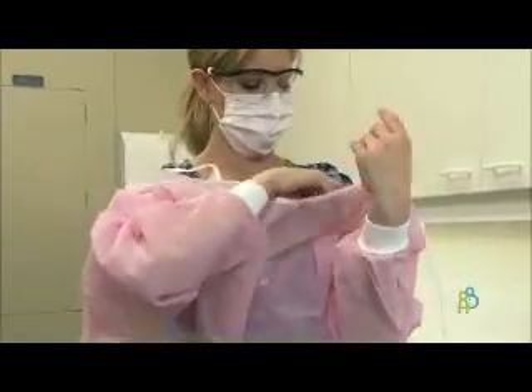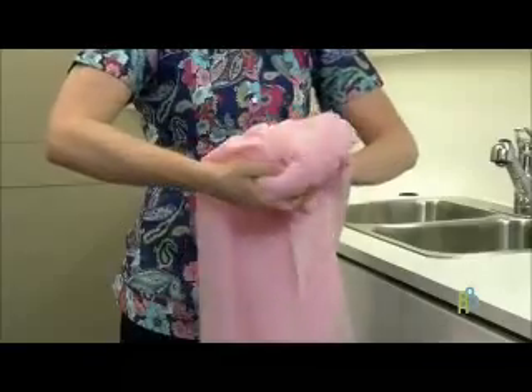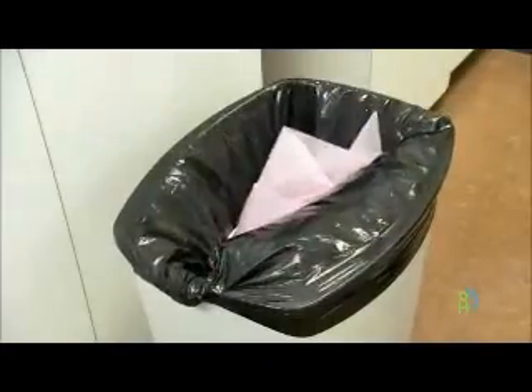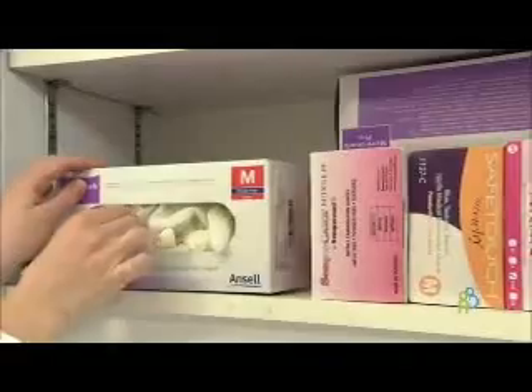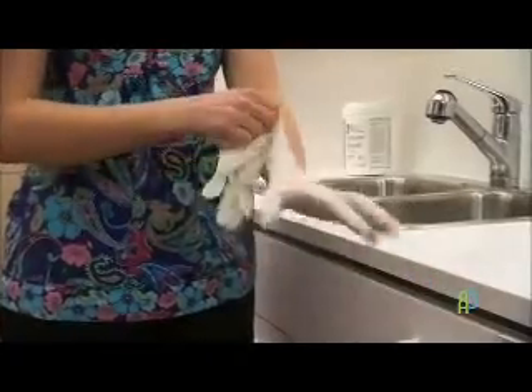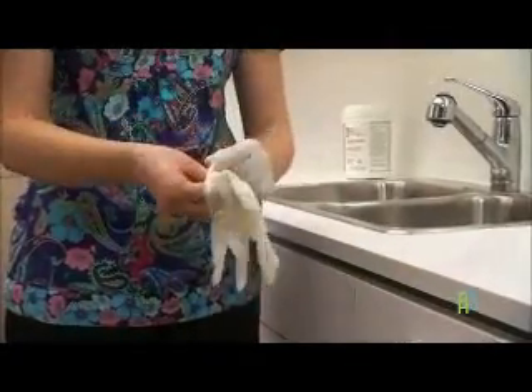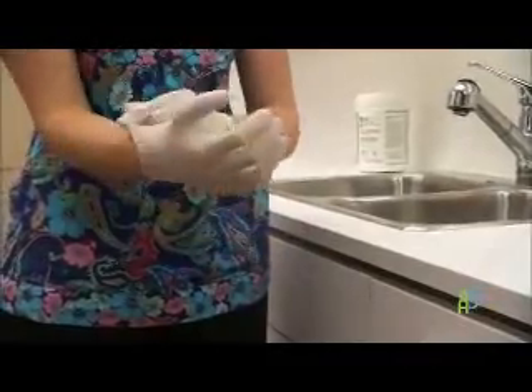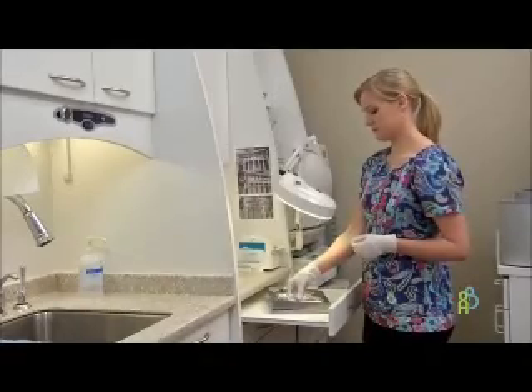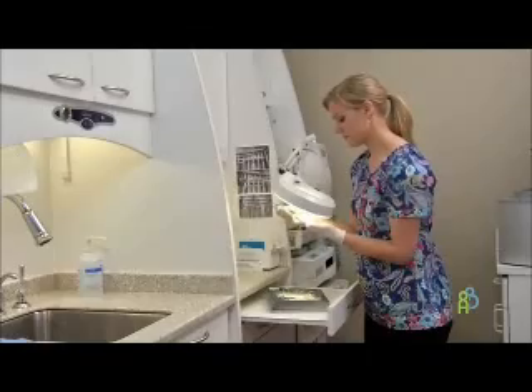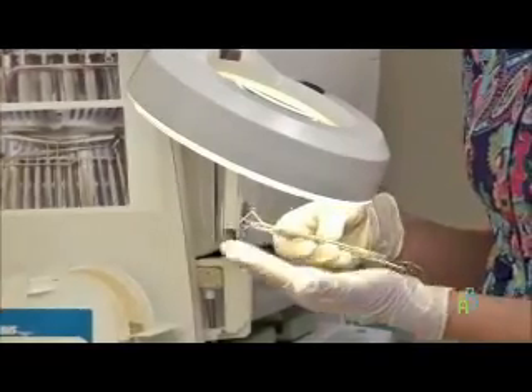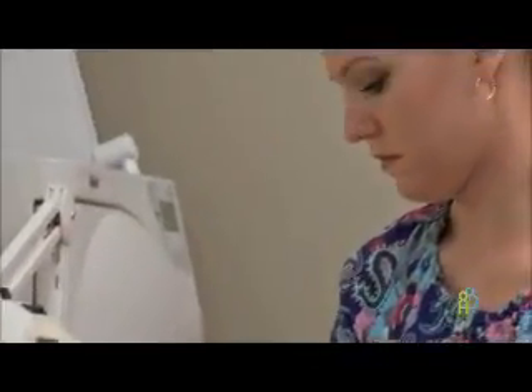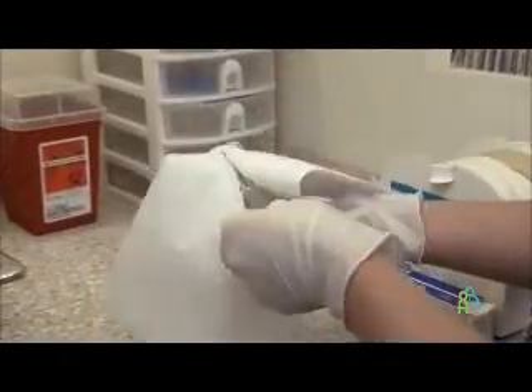There have been reports of adverse patient reactions to the cleaning chemicals when devices have not been adequately rinsed. Upon completion of the cleaning process, remove all PPE, perform hand hygiene, and apply clean gloves prior to drying, inspecting, and packaging the instruments for the sterilization process. At this point, the devices are clean but not disinfected. Prior to being packaged for sterilization, devices must be inspected and dried.